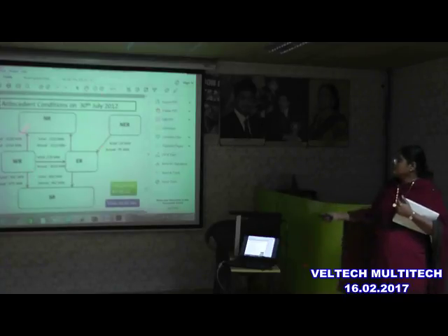But fortunately, southern region, can you see? Schedule was 968.35, actual was 962, and this was a separate grid, it was not tied to them. So when this got cut, it pulled ER away, and when ER got pulled away, WR also got pulled away. So what happened to these three regions? They all went together away from the system. That means they went into a blackout stage. But southern region was away from it. They are not connected to each other, so they got disconnected.